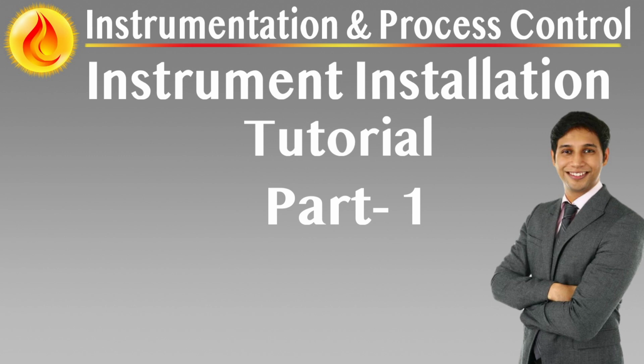For applications prone to plugging, such as slurries or waxy fluids, straight-through isolation valves, such as gate, ball, or plug types, are preferred to enable direct rodding and mechanical clearing of blockages from process connections.